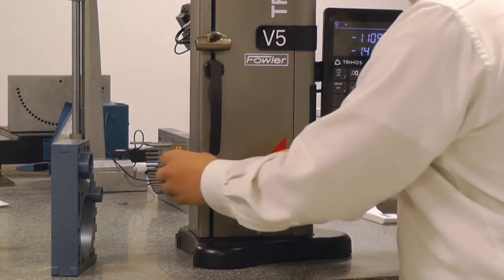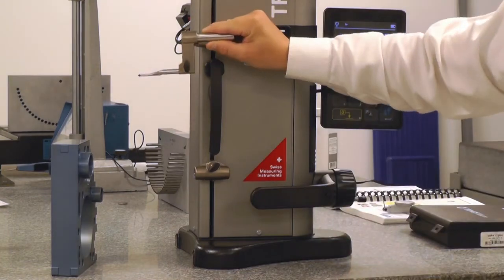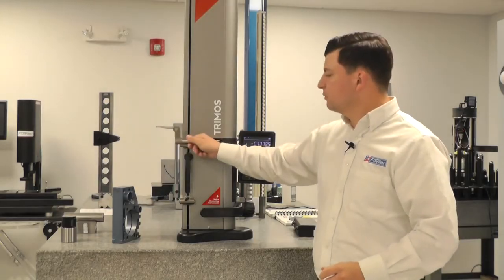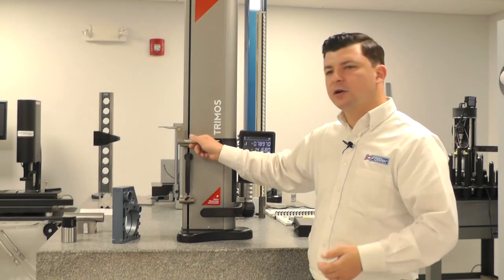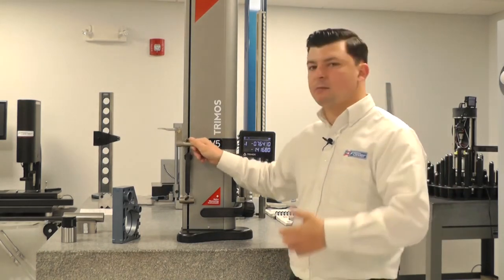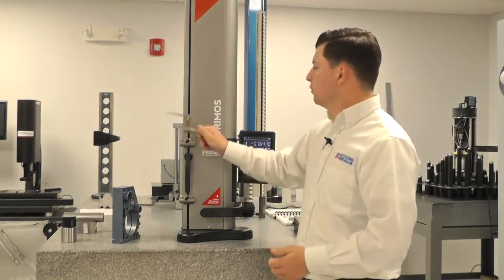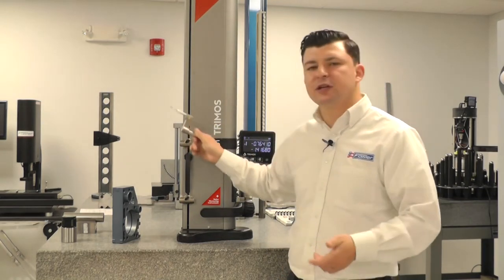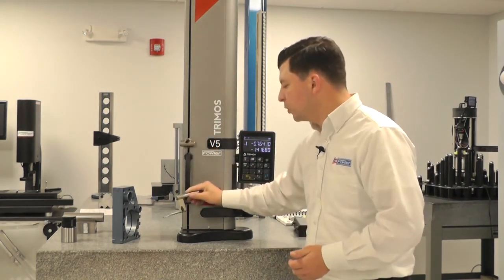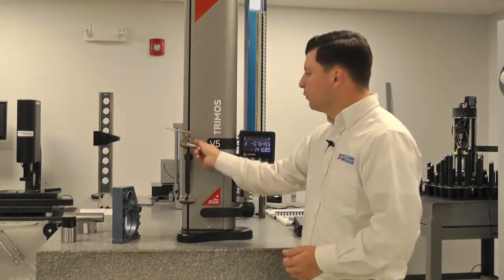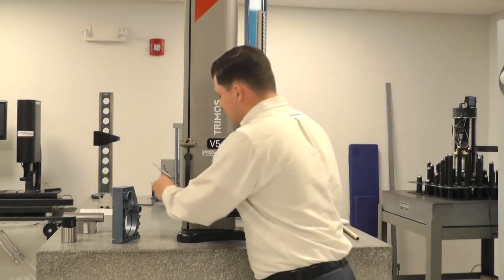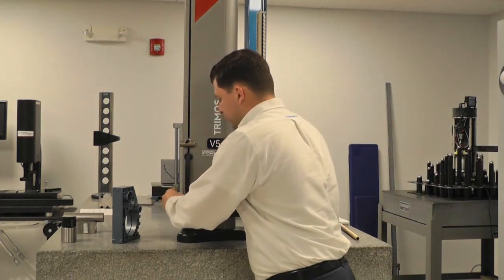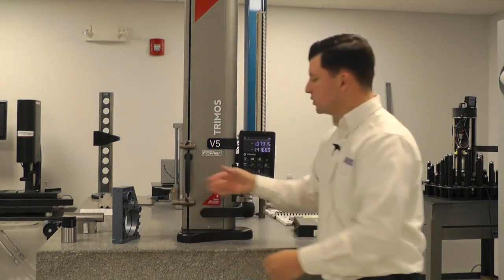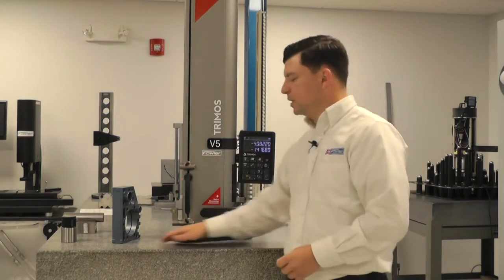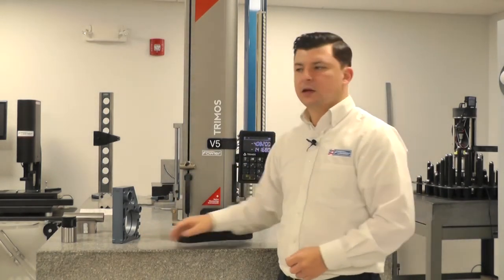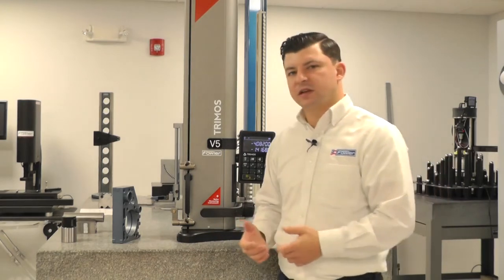From there, we can put it in our secondary probe holder, or we can invert it in our secondary probe holder. Inverting in our secondary probe holder is going to give us our maximum application range. On this particular gauge, we have a 0 to 28-inch direct measuring range, and a 40-inch application range. If we were to utilize any of these application positions, obviously we can no longer zero off of our plate.